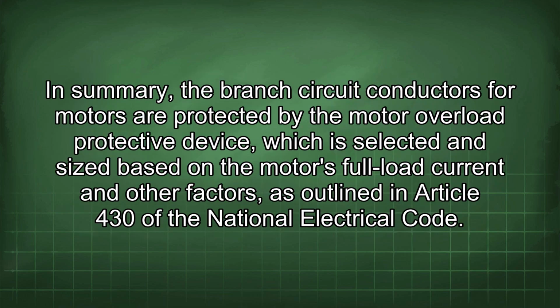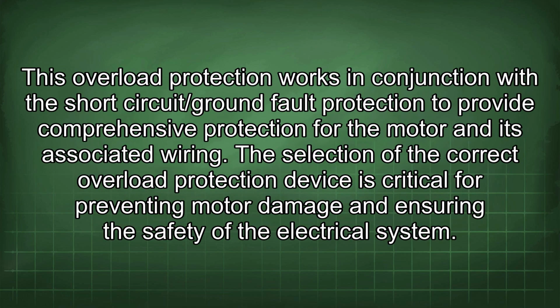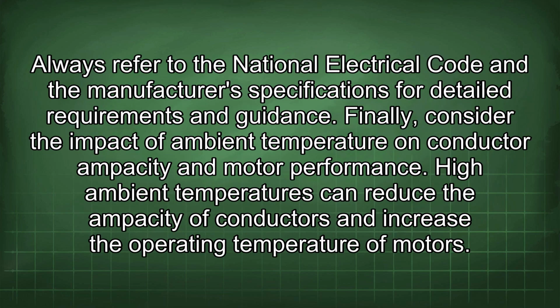In summary, the branch circuit conductors for motors are protected by the motor overload protective device, which is selected and sized based on the motor's full load current and other factors, as outlined in Article 430 of the National Electrical Code. This overload protection works in conjunction with the short circuit/ground fault protection to provide comprehensive protection for the motor and its associated wiring. The selection of the correct overload protection device is critical for preventing motor damage and ensuring the safety of the electrical system. Always refer to the National Electrical Code and the manufacturer's specifications for detailed requirements and guidance.